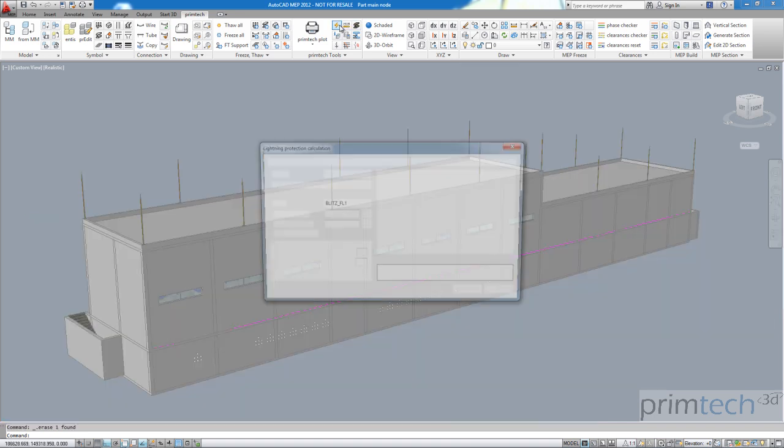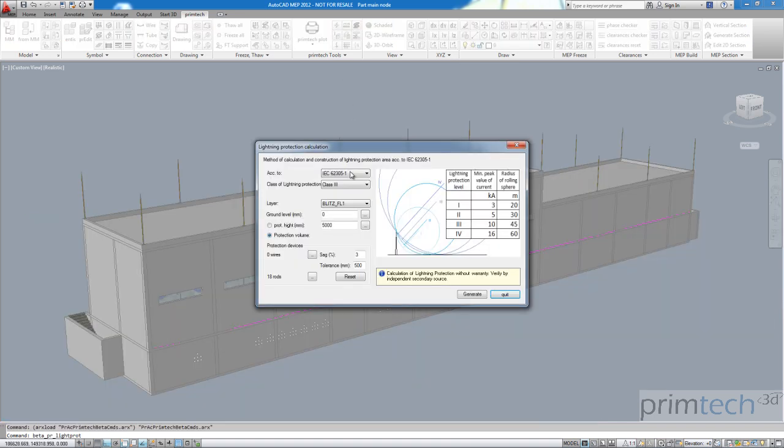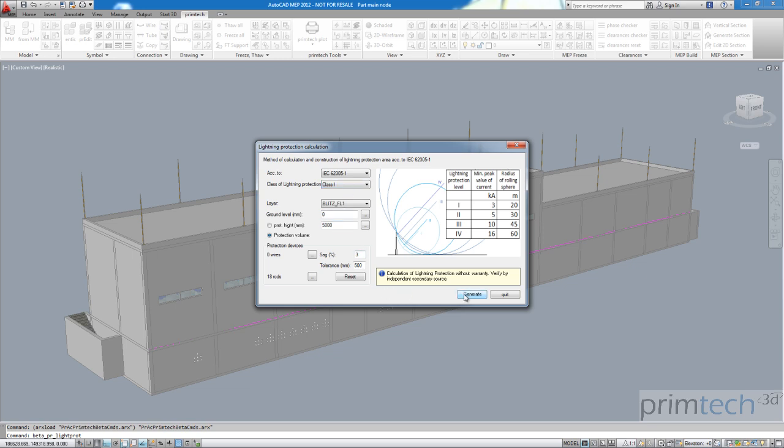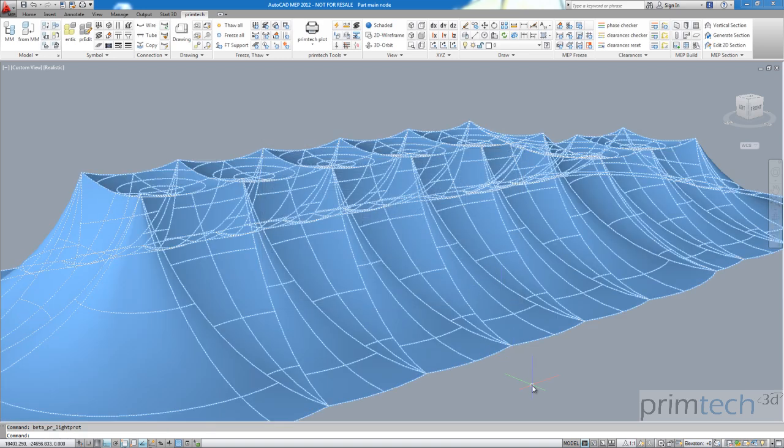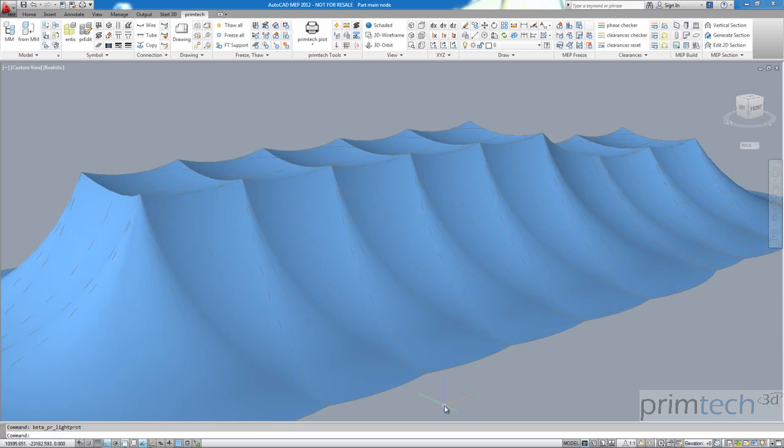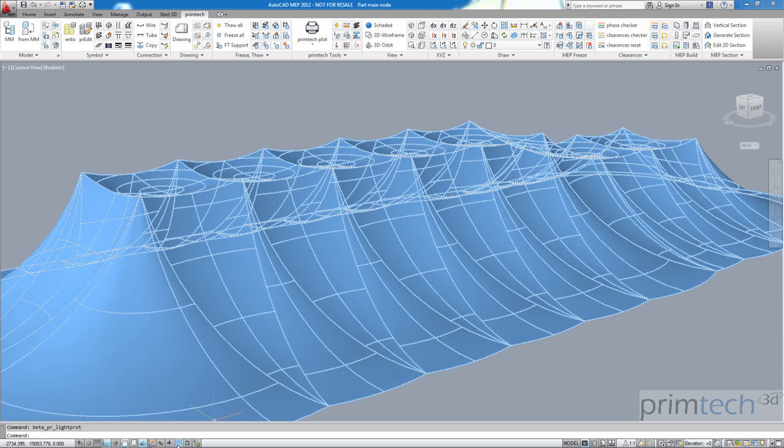Now let us take the same calculation but this time using class 1 lightning protection and generate again. Once again it won't take long. There it is and as you see everything is sufficiently protected here with the gas insulated substation beneath it.